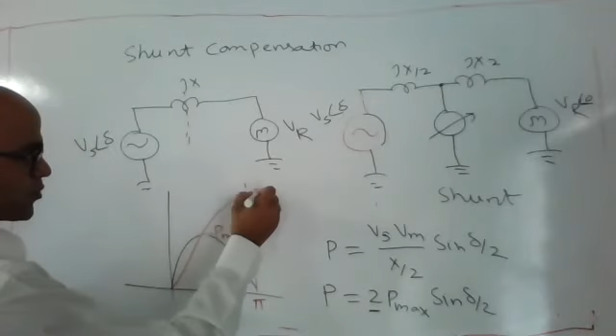If you draw it, initially P equal to Pmax sine delta is this. This is the Pmax in the first case, when there is no compensation. If you do compensation, then delta will become 2 pi, where in the first case it was pi. So the half cycle will have a 2 pi time period, and its power is also double: 2 Pmax and delta by 2. So this is the curve for P equal to 2 Pmax sine delta by 2, and this black one is for P equal to Pmax sine delta. These two are applicable only when the magnitudes of Vs, the shunt compensation voltage, and Vr, all three voltages, have the same magnitude. Under this condition this curve is valid, otherwise it will not be valid. It will become complex.